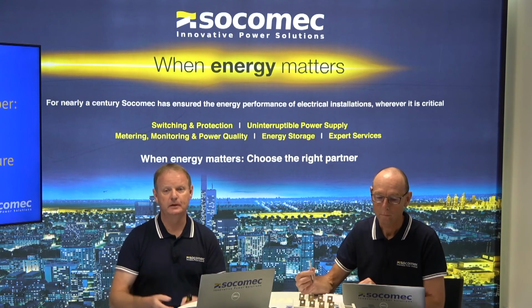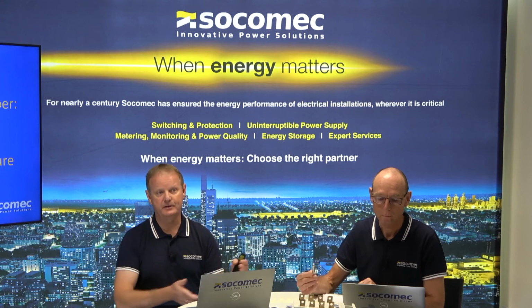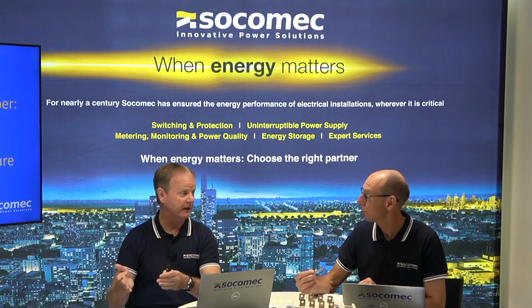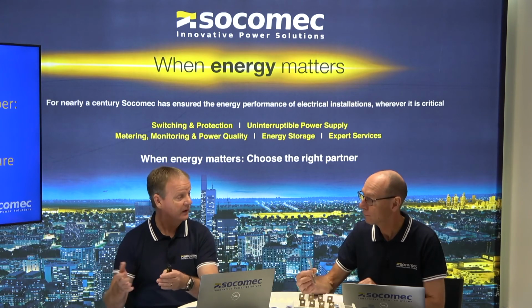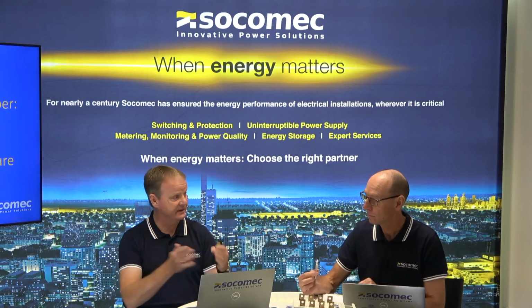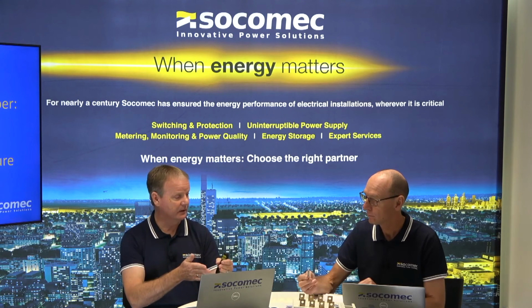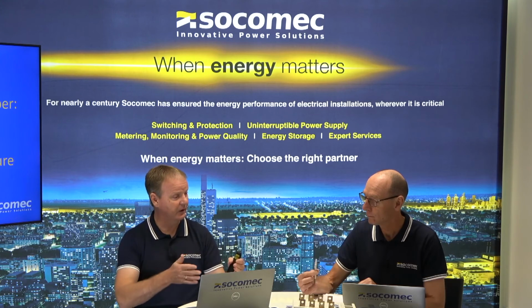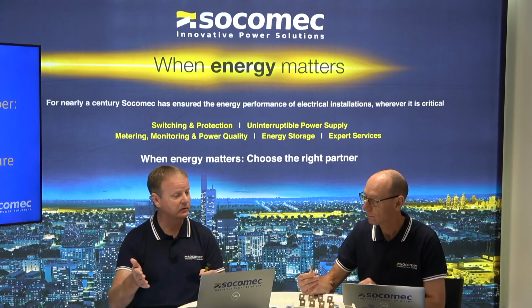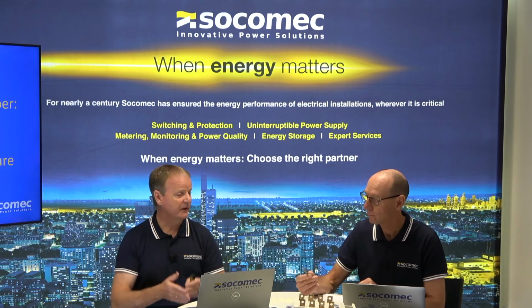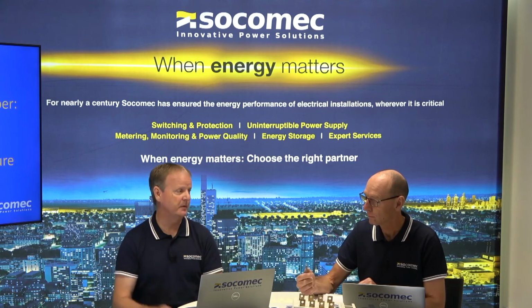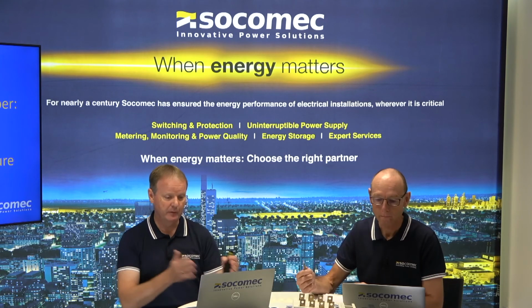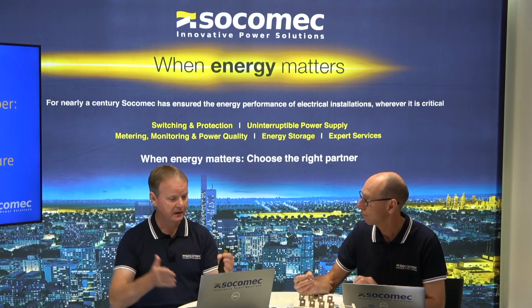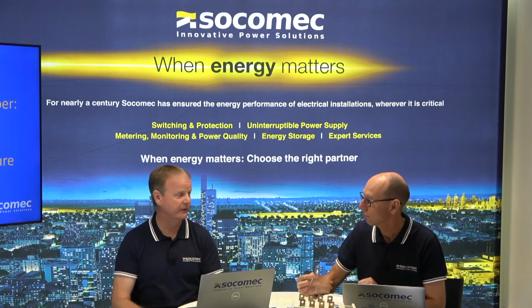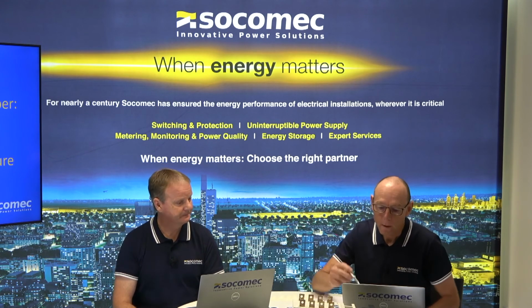So if in a fire situation it automatically goes to the generator, then a single line is fine. But if the installation stays on the transformer and there is a fire incident and you need that second source and you lose the transformer, if you have a single line, you won't be able to transfer the power over. So it's a key point. A lot of people go for the single line, not realising that there's not enough redundancy if you don't go for the dual line.